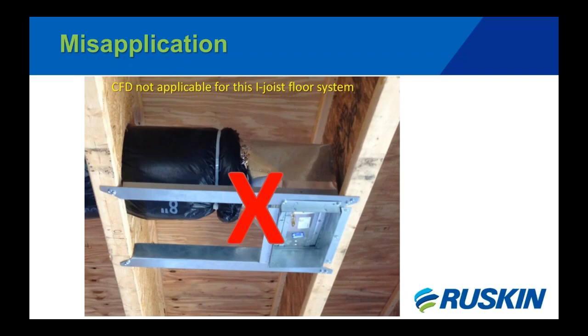Another question that comes up is, are the CFDs dynamic rated? We talk about dynamic rating and static rating on fire dampers, but ceiling radiation dampers are not tested in heated airflow conditions. So they do not go through any kind of airflow or pressure test requirements. So we would say ceiling radiation dampers are not dynamic, they're only static rated. The UL standard itself assumes that there's no air movement.